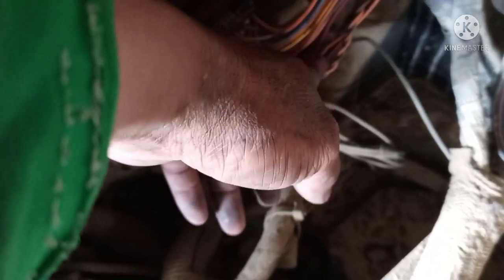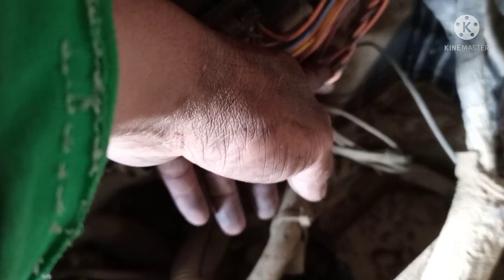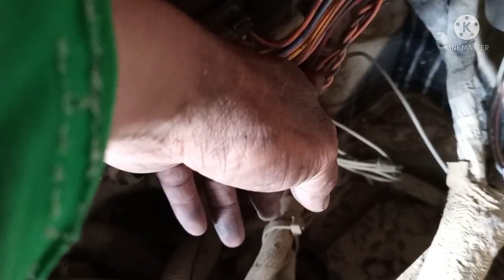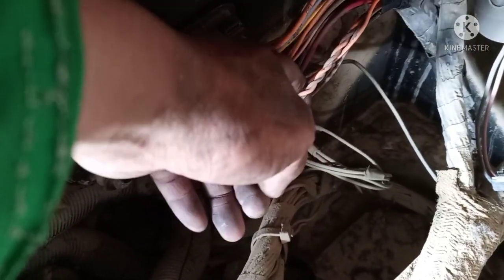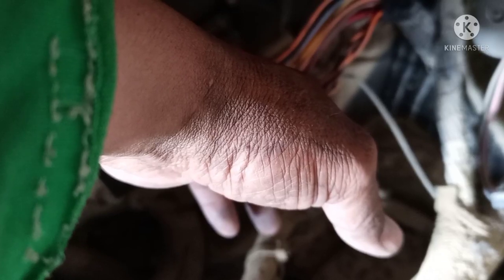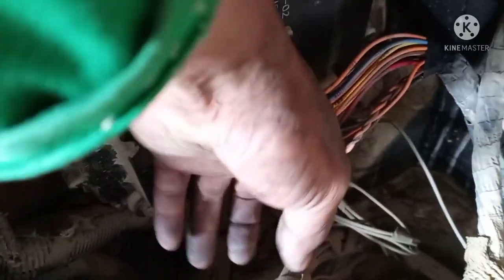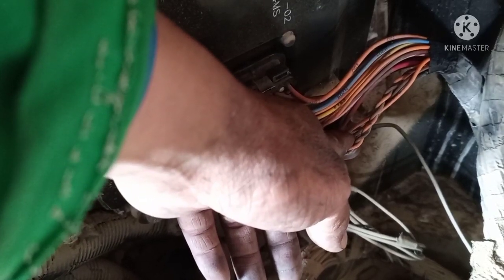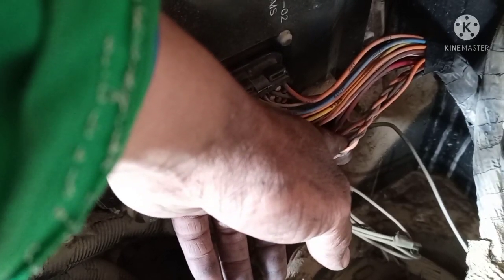Thousand ohms in resistance or higher, it is okay. But normally we need to find out 5000. So the line, it is orange. I found nothing. It is zero. No communication from engine ECM to here in this implement. Okay, here's the implement. And then the brown color, I found a continuity around 1400. Oh no, sorry, 1800, the continuity.